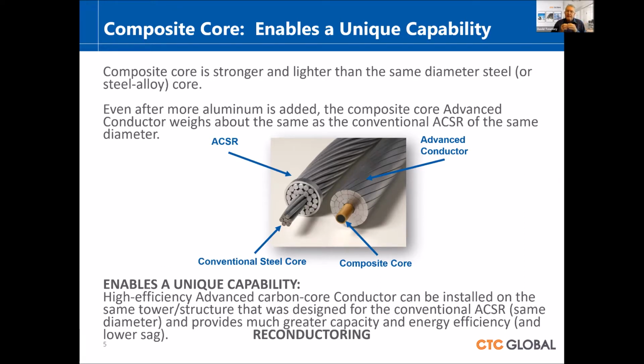And that's what enables a very unique capability in the current market, because these high efficiency advanced conductors can now be used on the same structure. That structure was designed for the weight of that ACSR of a certain diameter. And now it can be changed wire for wire on the existing structure and be able to bring much more capacity, much more efficiency to that right of way.